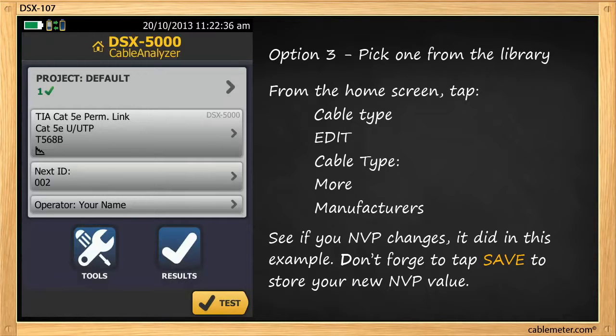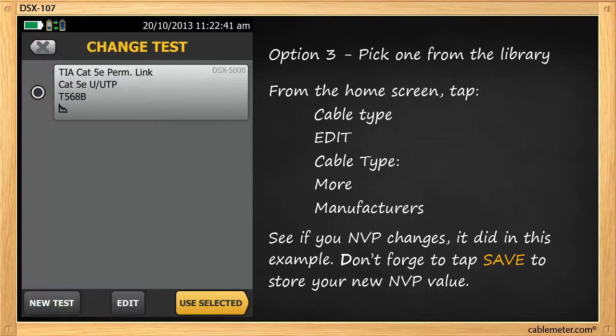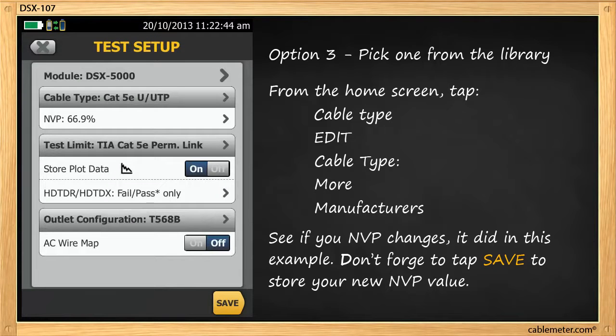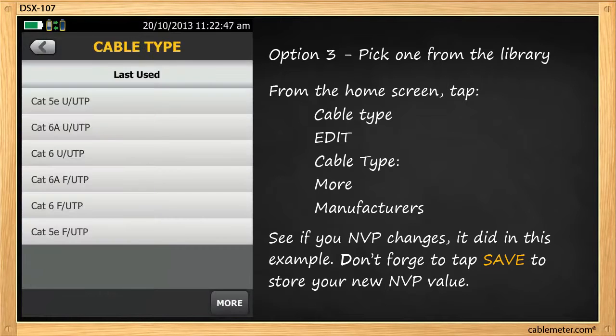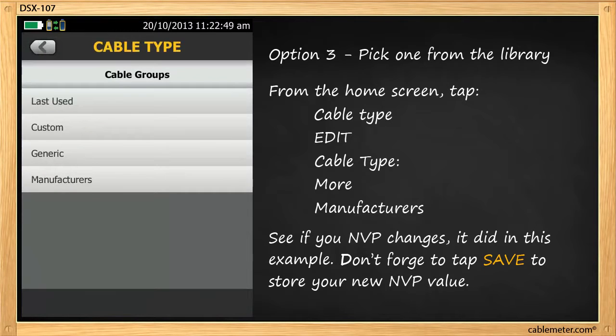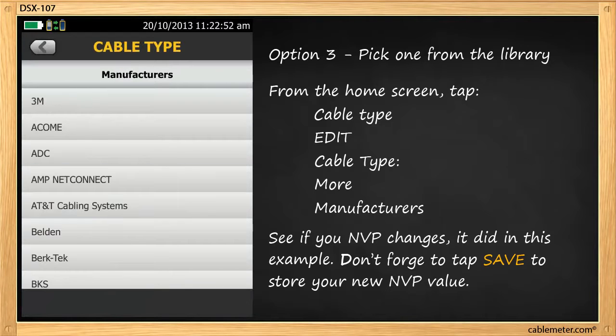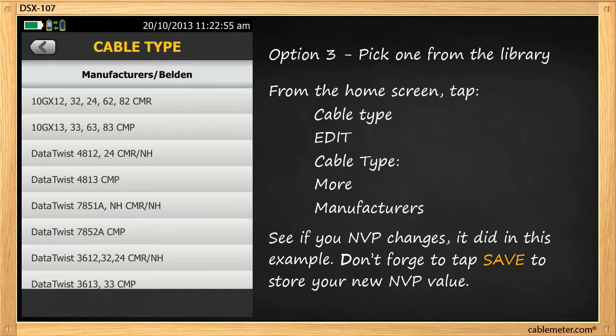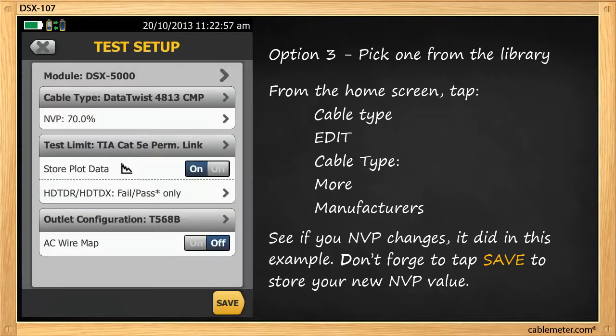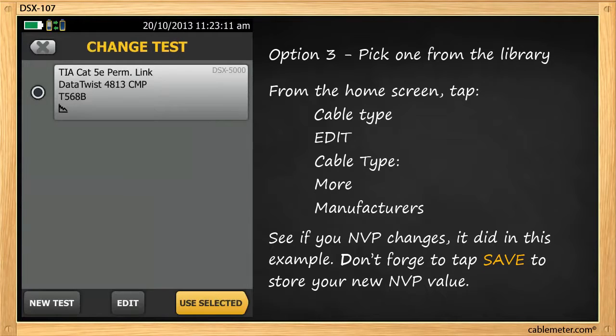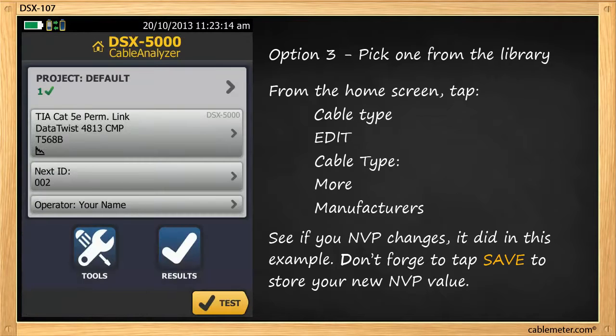The final method is to choose one from the cable library. From the home screen, tap your cable type, Edit. And where you see Cable Type, tap More. You'll see manufacturers at the bottom. I'll randomly pick Belden and select a cable. You'll see the NVP value changes to 70%. When you change the cable type in the library, it looks up the database in the tester and presents you with the value that's in there. Tap Save, select it, and you'd be ready to begin testing.